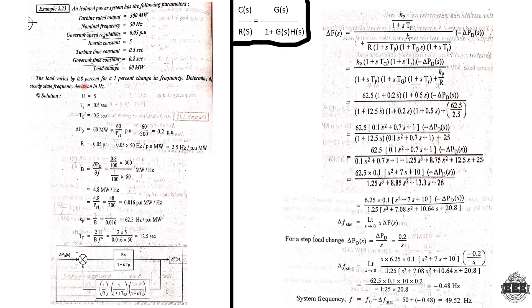The B value is delta Pd divided by delta f. For a 1% change in frequency, load changes 0.8%. So B = (0.8/100 × 300) divided by (1/100 × 50), giving 4.8 MW per hertz. In per unit, dividing by 300 gives B = 0.016 per unit MW per hertz.